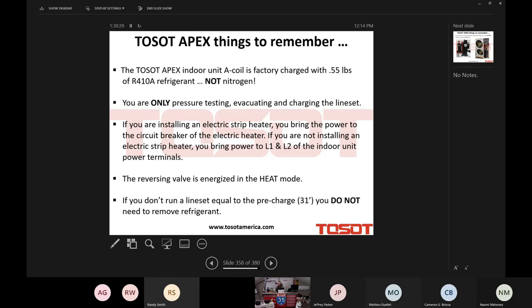The reversing valve is energized in the heating mode. If you don't run a line set equal to the precharge, 31 feet, you do not need to remove refrigerant. That's a Tosot thing, and that's true for either mini split or Apex. One of the design features of the Apex and the multi-zone outdoor units of the mini split world is two accumulators. Now, if you remember early on when I showed you that flow chart with all the components, one of the accumulators is actually called the flash tank.